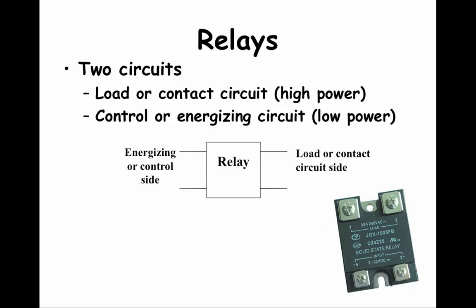Relays have two circuits attached to them. One circuit is called the load or contact circuit, which is connected to the device that the relay is turning on or off. The other circuit is the control or energizing circuit, connected to the controller. In the lab, you will see relays connected to the digital input and output side of the PDEC-55. The connections to the PDEC-55 will be on the energizing or control side of the relay, while the load side will be connected to a fan or light bulb. The control side usually has much lower voltage, so it is considered the low power side, while the load side is the high power side.